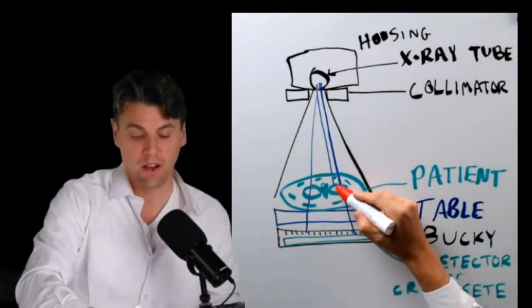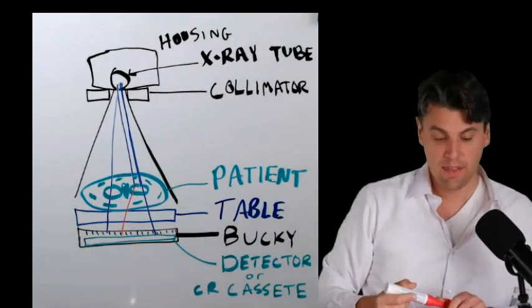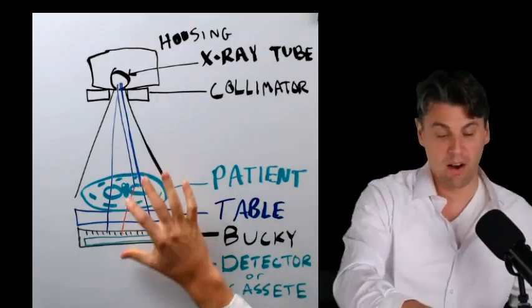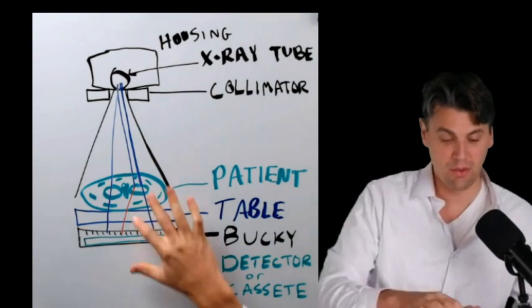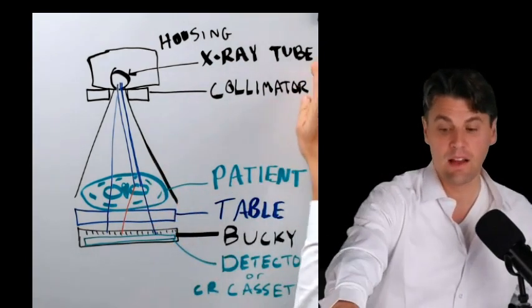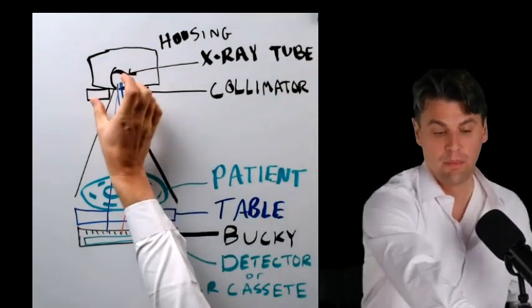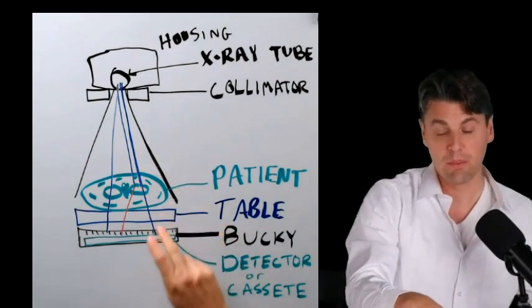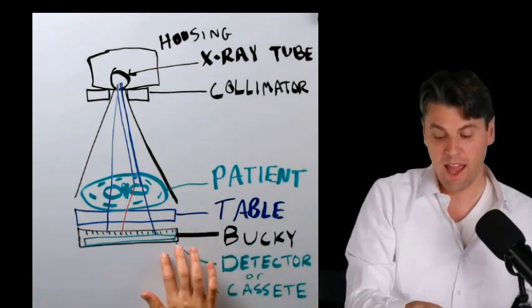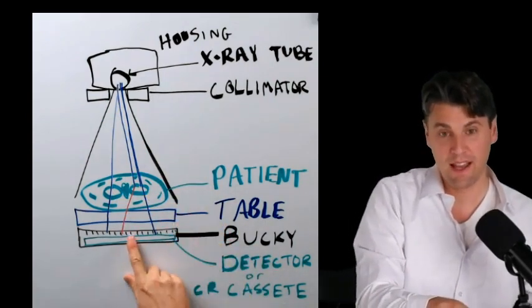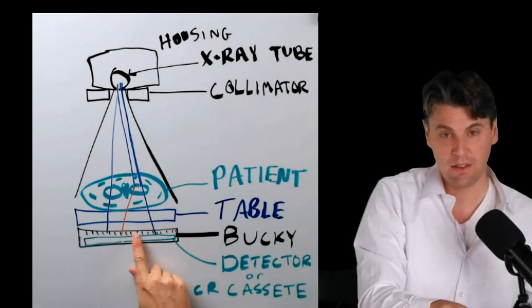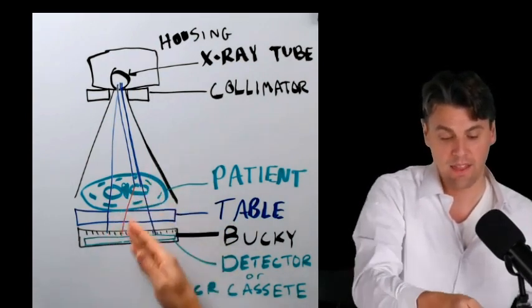Sometimes there's x-rays that are going to get scattered in the patient. That's going to lead to a background haze in our image due to scatter. But at a high level we go from x-ray tube, pass through the collimator, through the patient, through the table, and then we have what we call an anti-scatter grid here which is little septa to try and block that scatter.